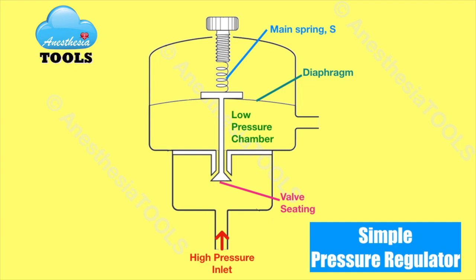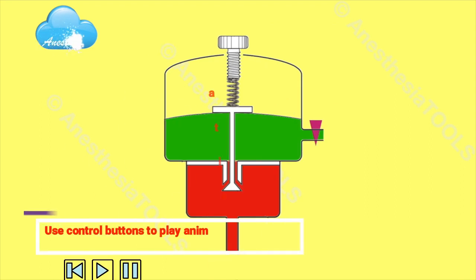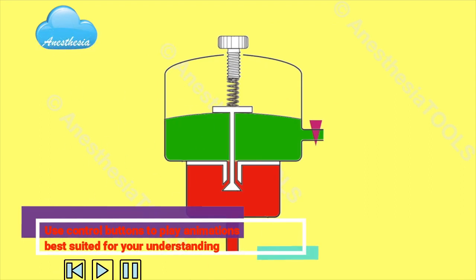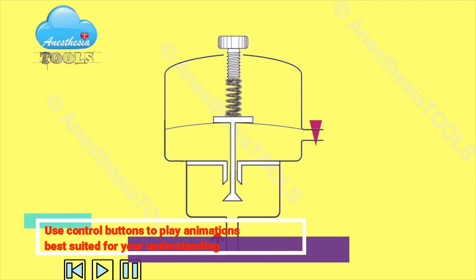When there is sufficient increase in pressure, the diaphragm moves and the valve closes. The pressure at which the valve closes can be preset by adjusting the screw and altering the tension in the spring. Now let us see the graphical illustration of the working principle of the pressure regulator.